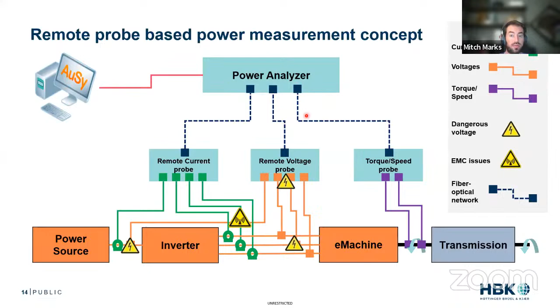What do these look like in reality? So they're these little boxes, maybe 20 centimeters by 10 centimeters, maybe 30 centimeters by 10 centimeters. They'll offer 5 voltage ranges up to 2 kV. So we're going to that higher voltage. They'll be available in 2 megasample or 20 megasample sample rates. So you can measure that really high rates, and you can get that highest quality measurement. And you can use these as a scope for many of your motor control needs. So again, we're replacing multiple instruments with one. Again, further simplifying your cabling, simplifying your software, simplifying your safety and your EMC hazards.